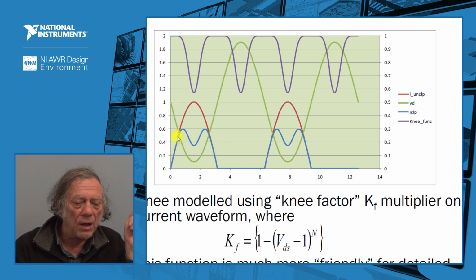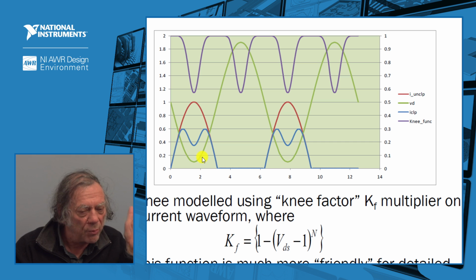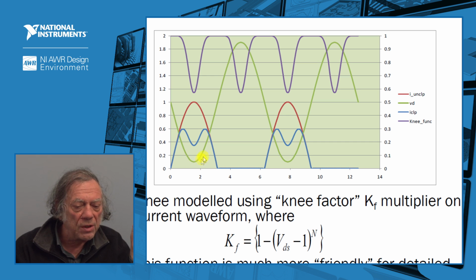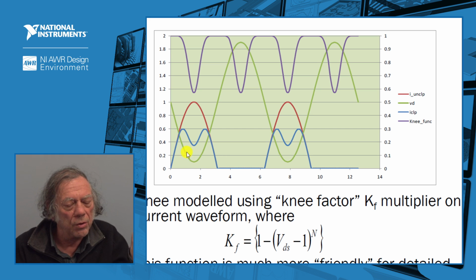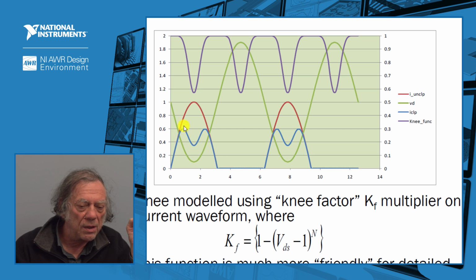However, if we have a sinusoidal voltage, and let's assume we've short-circuited our harmonics, we will clip that current as the voltage drives the device into saturation. What actually happens is the voltage still carries on hovering - it never really reaches zero - but as we increase the load, the device moves more into the clipping region, and you start to get these kinds of waveforms.